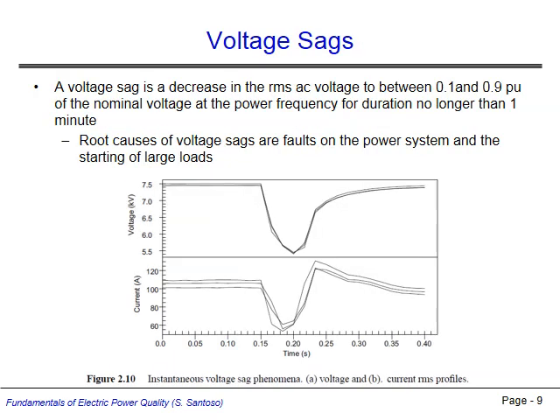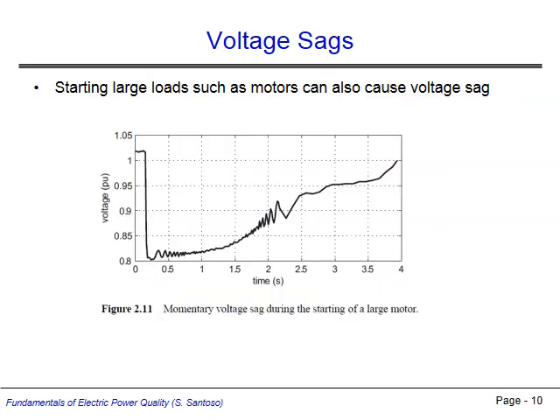Voltage sags occur when the RMS voltage magnitude falls to between 10% and 90% of the nominal value. Short circuit faults on the system are usually the cause of voltage sags, though they can also occur due to the inrush current associated with the starting of large loads, such as motors. The figure shows a voltage sag event, with all three phase voltages sagging to about 0.7 per unit. Here is another example of a voltage sag, this one caused by the starting of a large motor. The motor draws a large amount of inrush current as it starts, dropping the voltage upstream until the current diminishes and voltage returns to nominal levels.